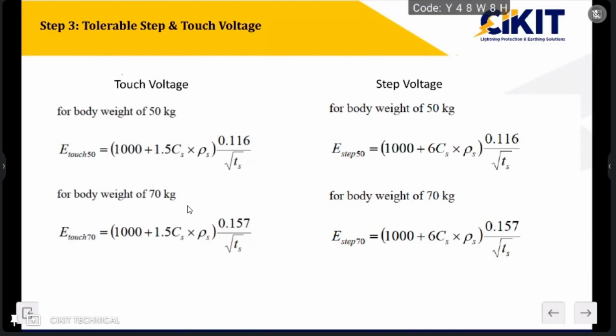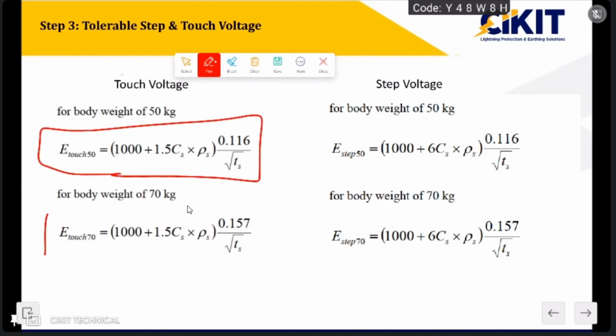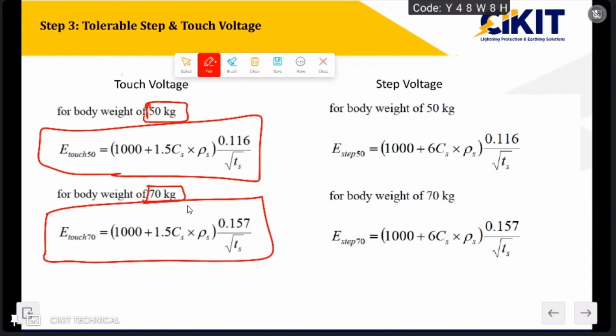Now, calculating the tolerable step and touch voltages including the Cs value: in the previous formula, we did not consider the value of Cs, that is the surface layer derating factor. But if I consider that, then the formulas for calculating the step and touch voltages are here. If you closely observe, the formula is different for different body weights. For 70 kgs, the formula will be different, and for 50 kgs, the formula will be different. This mainly depends upon the tolerable current limit of the human body.